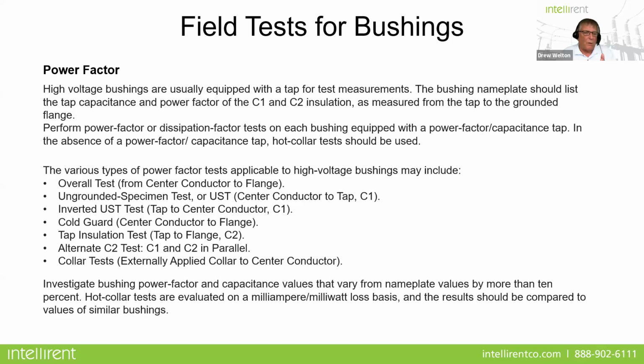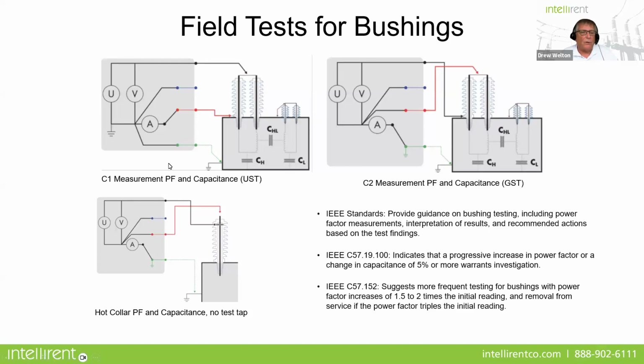There are various types of tests. An overall test, the center conductor to the flange. Typically, your C1 is going to be an ungrounded specimen test, or UST, from the center conductor to the tap. You can invert that, from the conductor back up to the tap, and then a tap insulation test. I've got a figure that illustrates it a little better. Here you'll see the connection diagram for a C1 test, where we go to the top of the bushing and measure here at the tap. And then, of course, your C2 test, and then a hot collar test as well.